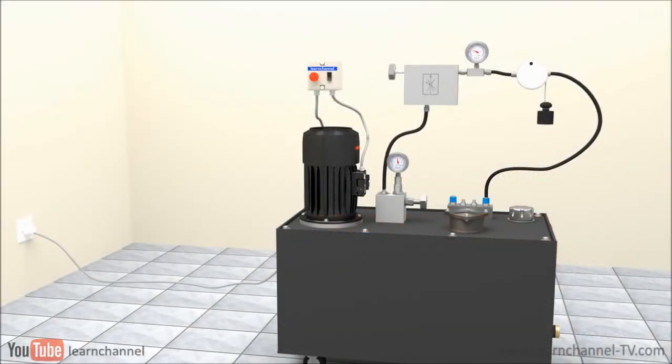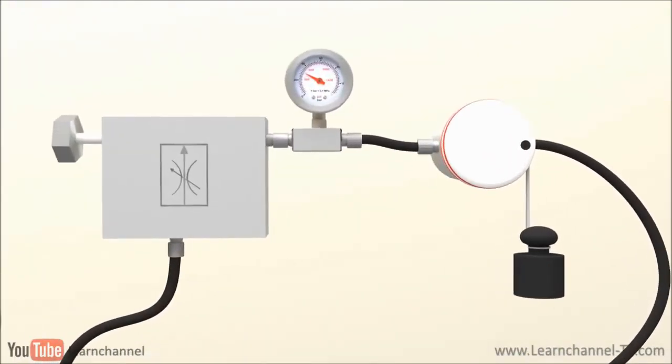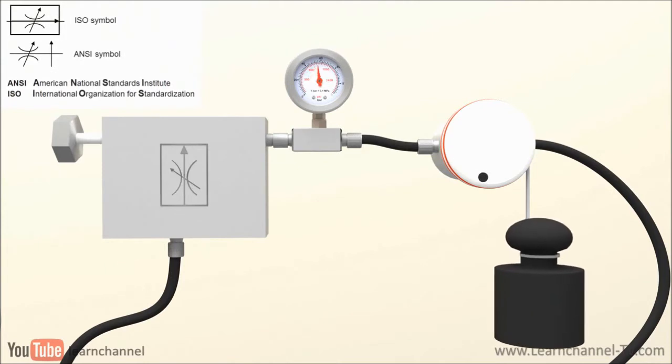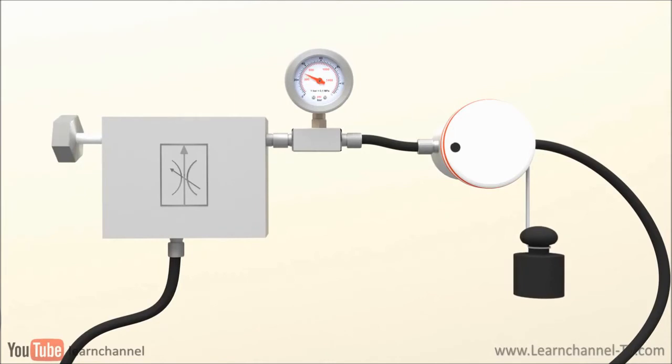Unfortunately, using a simple throttle leads to change in volume flow when load changes. So if you want to keep the speed of a cylinder or hydraulic motor constant, even with different loads, you should use a pressure compensated flow controlled valve. Or to say it another way, a pressure compensated flow control valve maintains an almost constant flow rate in spite of pressure changes across the valve.